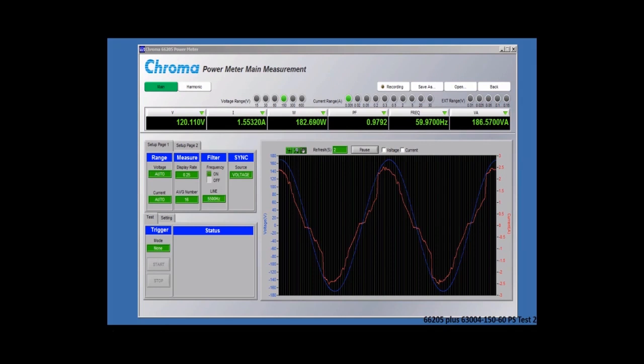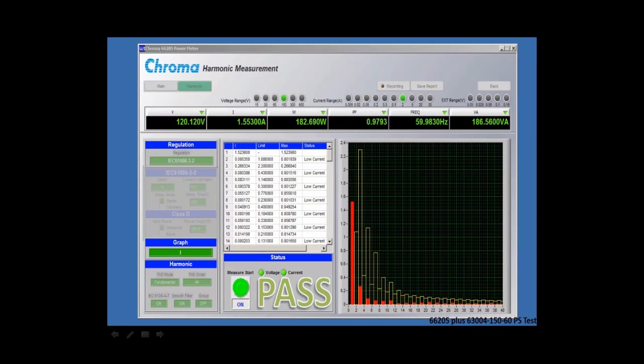When we're measuring harmonic distortion, you can go to this screen and it's going to give you the numerical data that you can see here in the center. Again, it can all be recorded to a text file. You can test it per the IEC 61000-3-2 limits, and you can also set the different classifications for IEC 61000-3-2. Here I've got it set to Class A. I'm showing the current graph, and the yellow lines you see here are the limits for IEC 61000-3-2, and the red are the actual measurements for each harmonic, each individual harmonic, and it shows how it reflects to the actual standard. And here you can see that both voltage and current are passing.